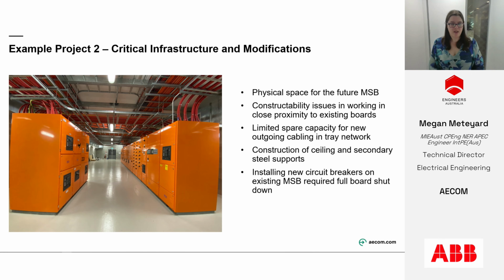We had to add approximately 14 metres of new main switchboards into that space. The reality of constructing that in close proximity to the existing board posed some challenges around how the electricians could safely do that work. You can also see in the image a lot of existing cables on a fairly hefty cable tray network, supported from a ceiling with some secondary steel structure.